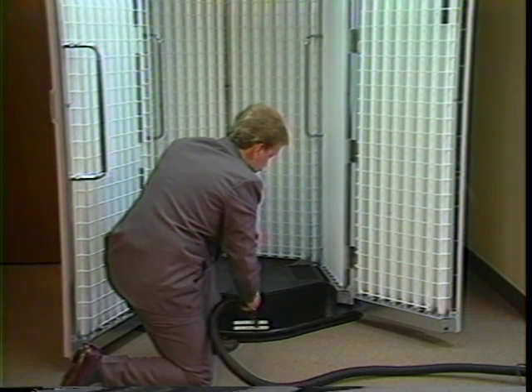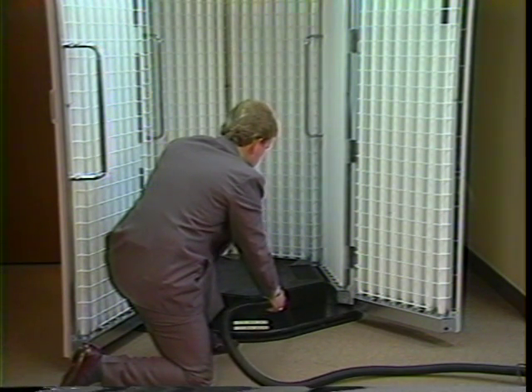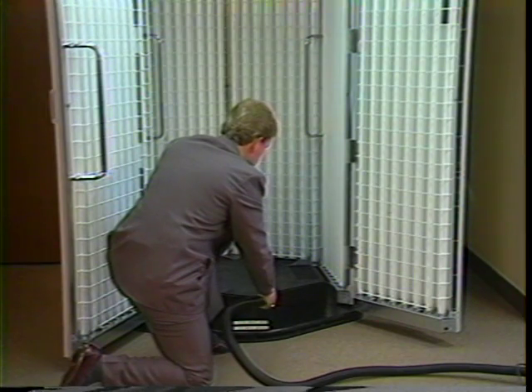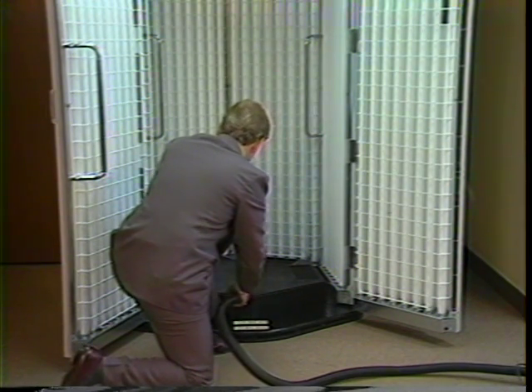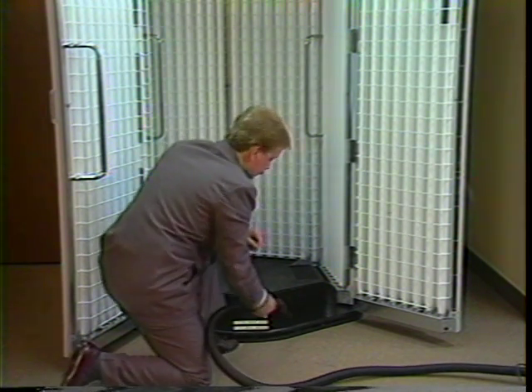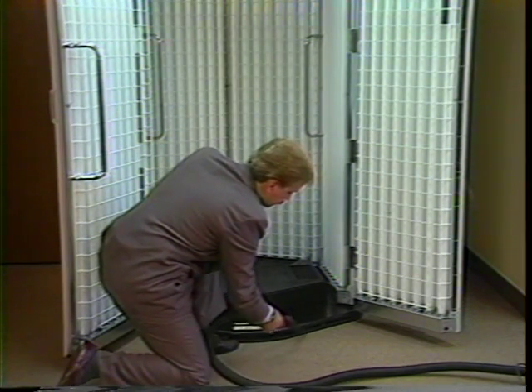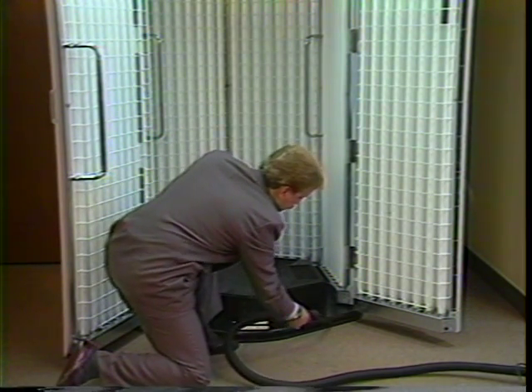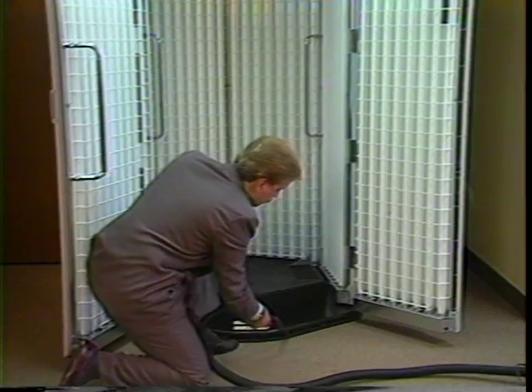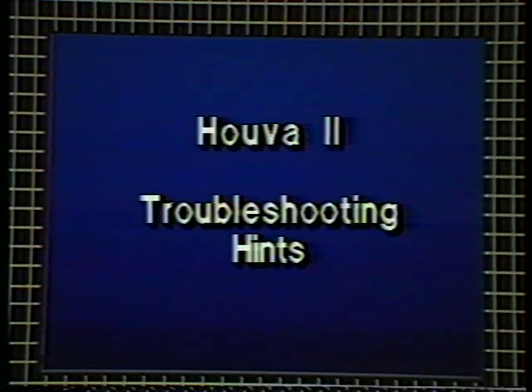How often the HOUVA II system requires cleaning depends on the number of patients treated. The greater the number of patients, the more often cleaning is necessary. The external vents around the base should be kept free of obstructions to allow the perimeter flow ventilation system to operate efficiently. All lamps, either fluorescent or incandescent, will burn out from time to time.